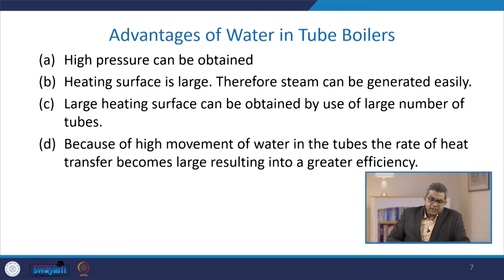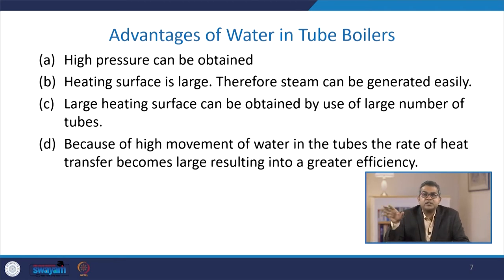There are certain advantages associated with water-in-tube type boilers. You can obtain high pressure. The heating surface is quite large, therefore steam can be generated easily. A large heating surface area can be obtained by using a large number of tubes, which you can embed accordingly. Due to the high movement of water in tube, the rate of heat transfer becomes large, resulting in greater efficiency.